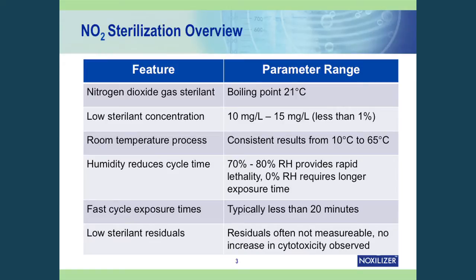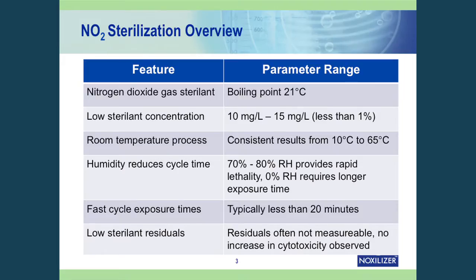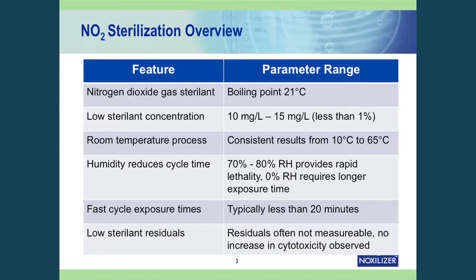It's a room temperature process and we don't have temperature control inside the chambers. We allow the chambers to equilibrate to room temperature, and we find consistent process results over a wide temperature range. Humidity, however, is an important factor. You can have a much faster process with humidity — typically 70 to 80% relative humidity inside the chamber during the exposure process. If the materials are sensitive to humidity, such as electronic components or biodegradable polymers, a zero humidity environment is also possible, but it does take longer. The slowest cycles at 0% relative humidity take about 4 or 5 hours.